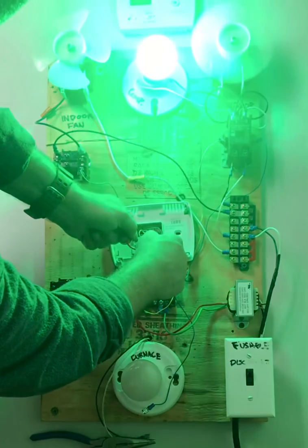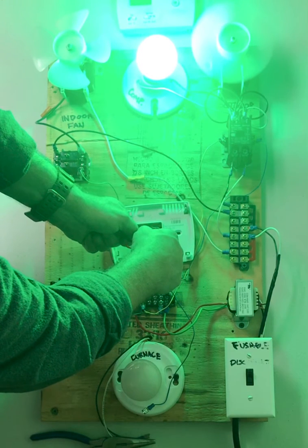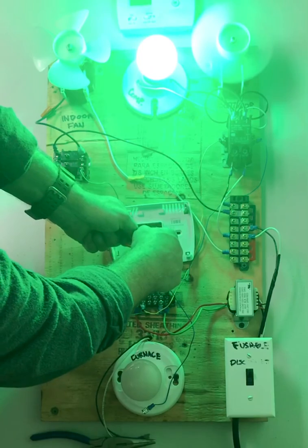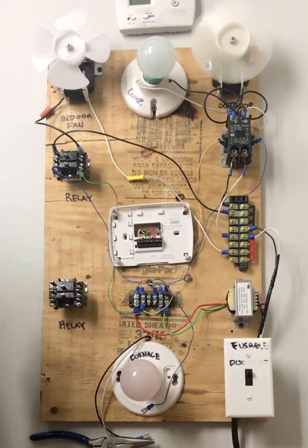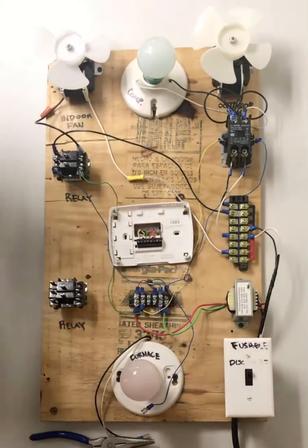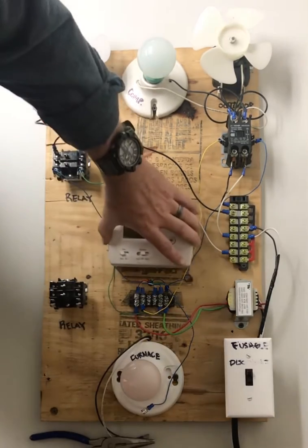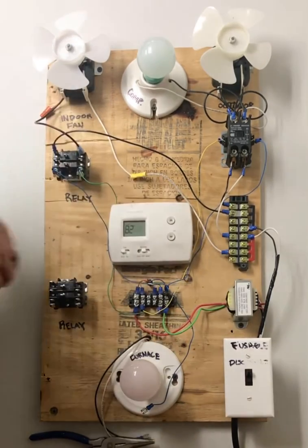and we see we're getting a cooling call. Our outdoor condenser's turned on, our compressor's turned on, and we're getting our cooling call. So at this point, you tell the customer they've got a bad thermostat, and you go ahead and install your new thermostat, and then you test it by making a cooling call.